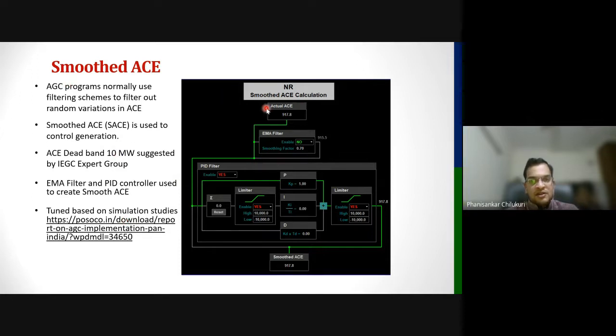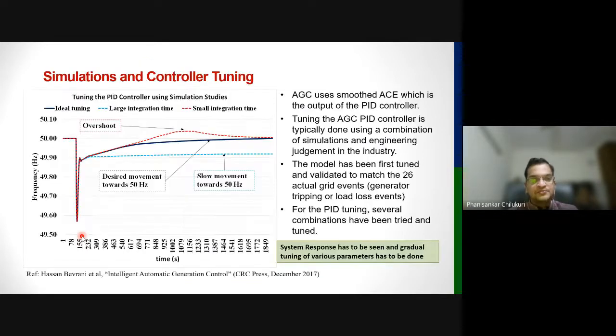For this area controller, we do not use the raw ACE, but we smoothen it. We use something called a smoothened ACE. We use an EMA filter and a PID filter as of now to smoothen this ACE, and we tune this PID controller using simulations. I've given some links you can read up. AGC uses smooth ACE, which is the output of PID controller. Tuning PID controller is typically done using a combination of simulations and engineering judgment. We have tried several combinations. If you do ideal tuning, it is nice, but if you use a large integration time, obviously the response would be sluggish. If you have a small integration time, there can be chance of overshoots.